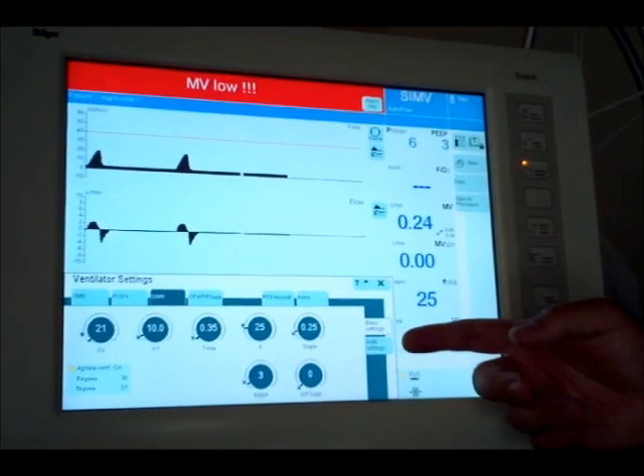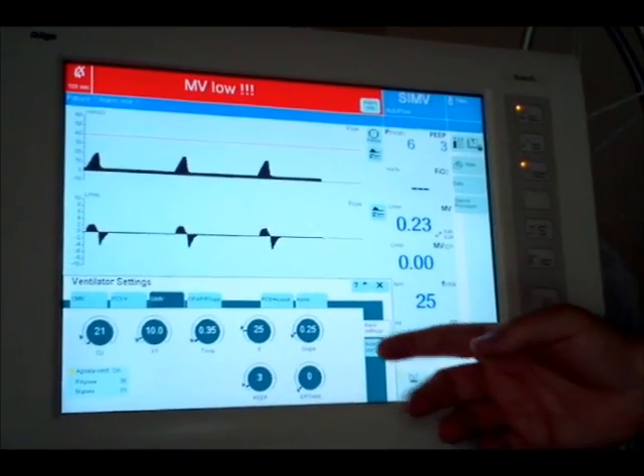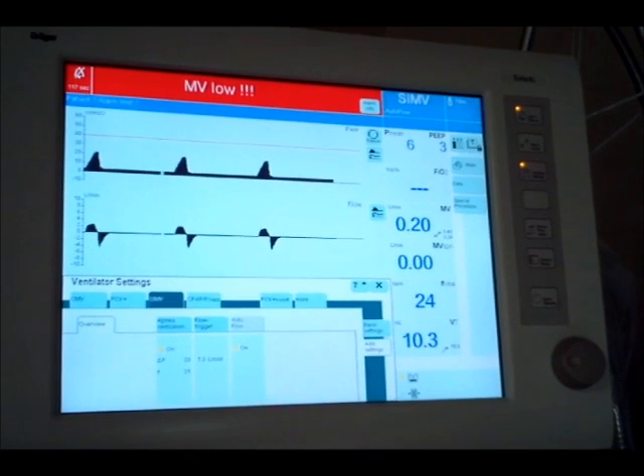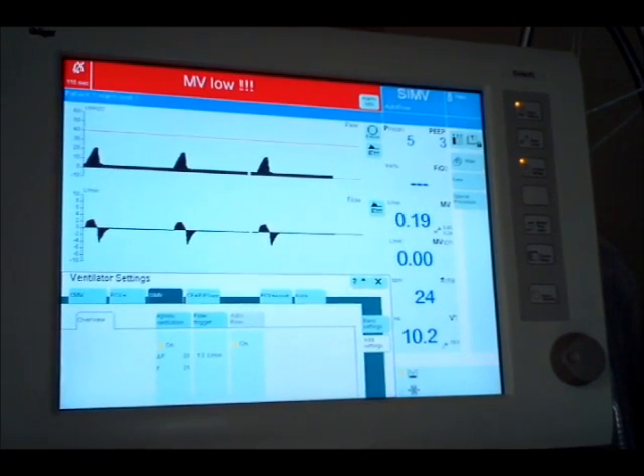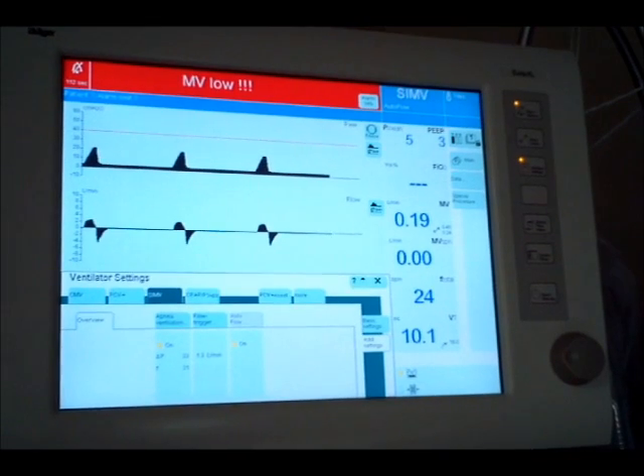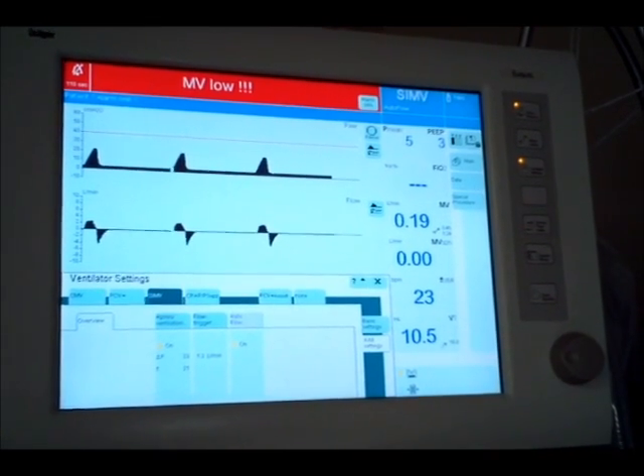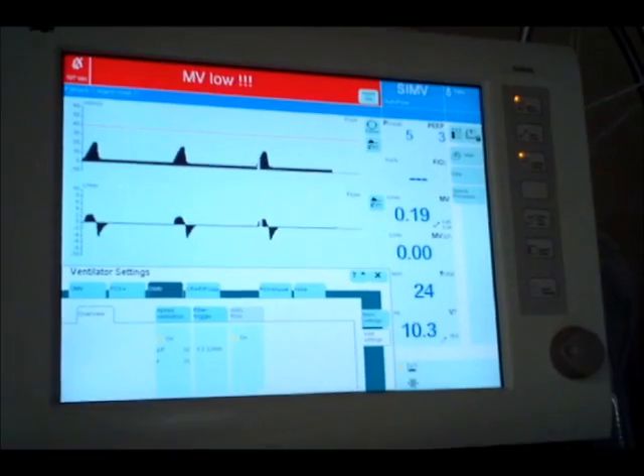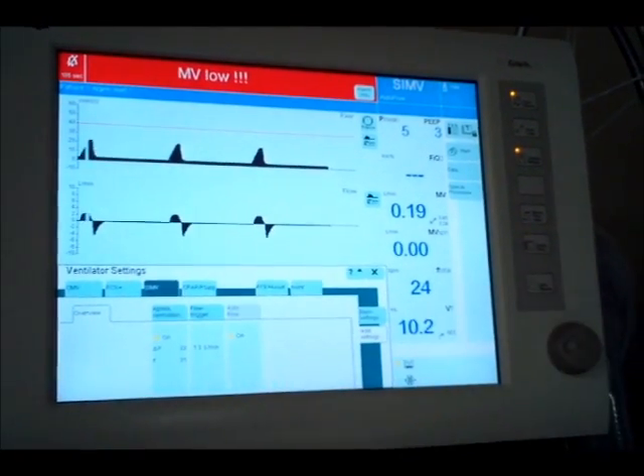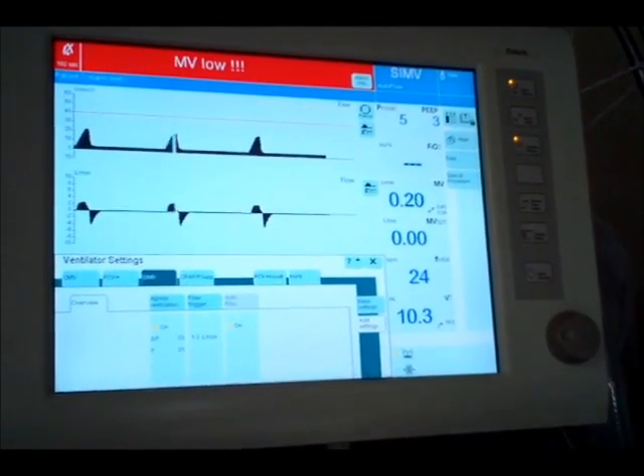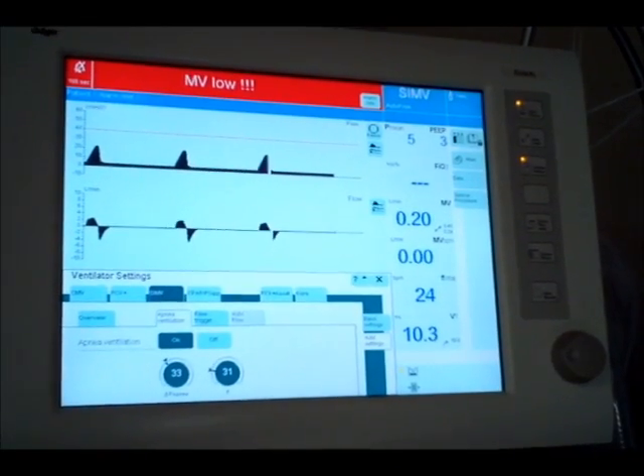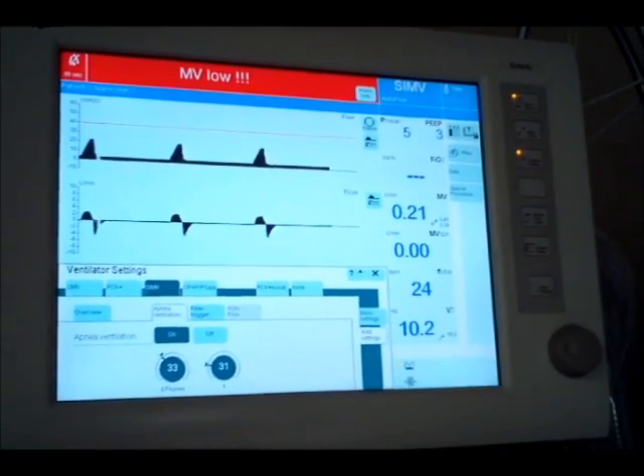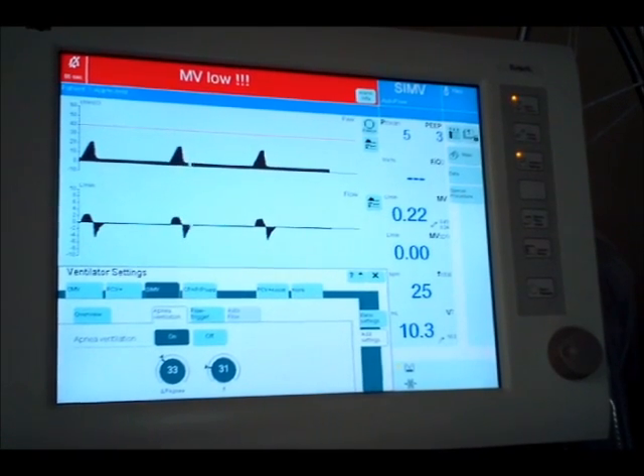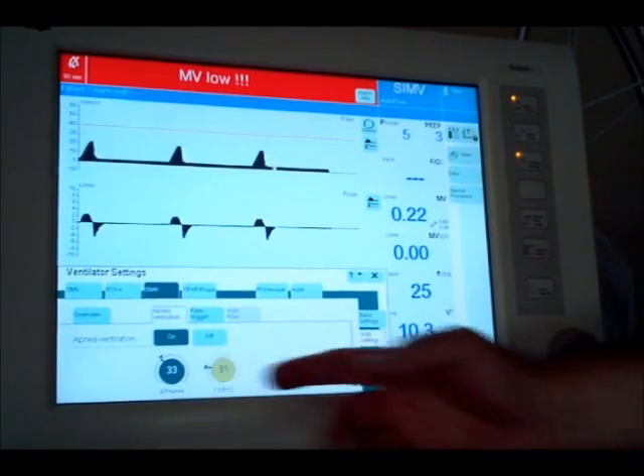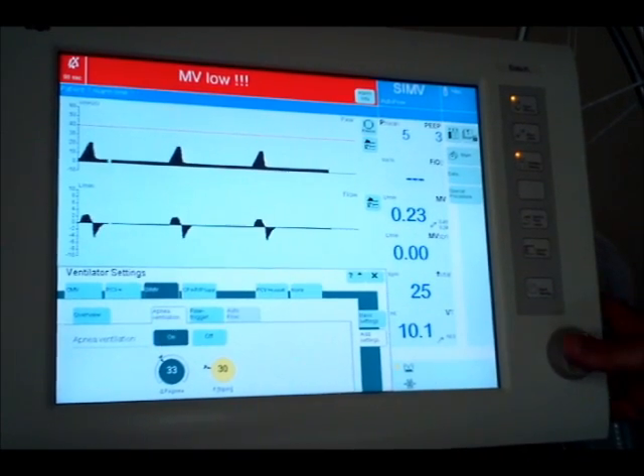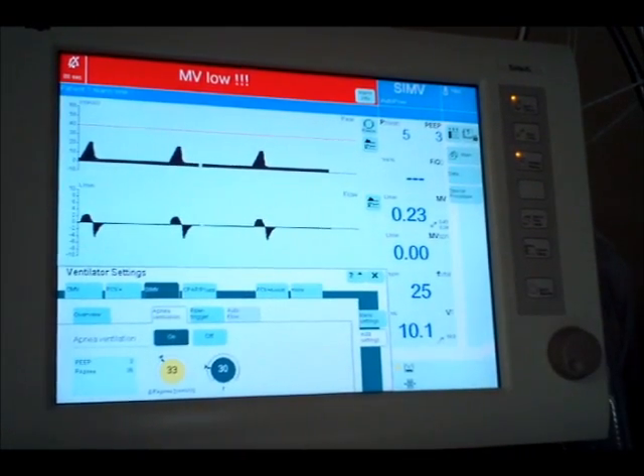Might not be a bad time to think about, since it's up there, my additional settings. Okay, notice there's something there now that wasn't there before. And there's actually something missing that was there before, but we won't dwell on that too much. Now, since I have spontaneous breathing mode, I have apnea ventilation active. So what we want to do is select our apnea ventilation and just make sure our pressures and our rate are acceptable for that. I might set a rate of 30. That's what we had them on when they were in. And then this pressure is a little bit high for me.